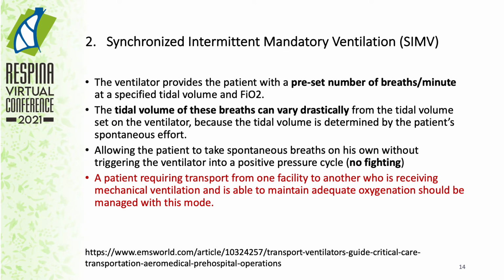The other mode is synchronized intermittent mandatory ventilation or SIMV, in which the ventilator provides the patient with a preset number of breaths per minute at a specified tidal volume and FiO2. The tidal volume of this breath can vary drastically from the tidal volume set on the ventilator because the tidal volume is determined by the patient's spontaneous effort.